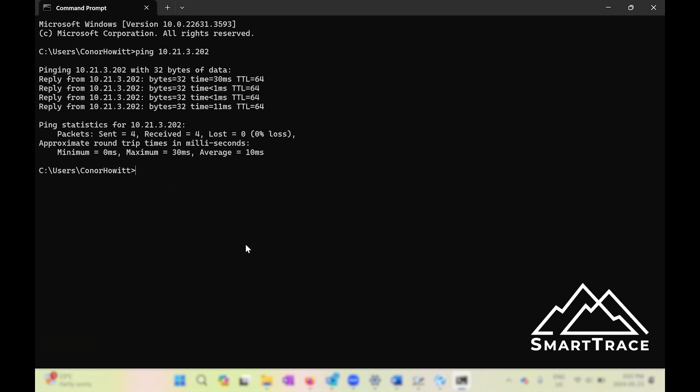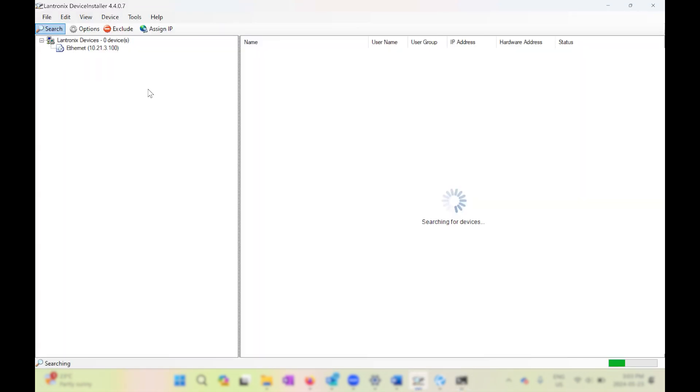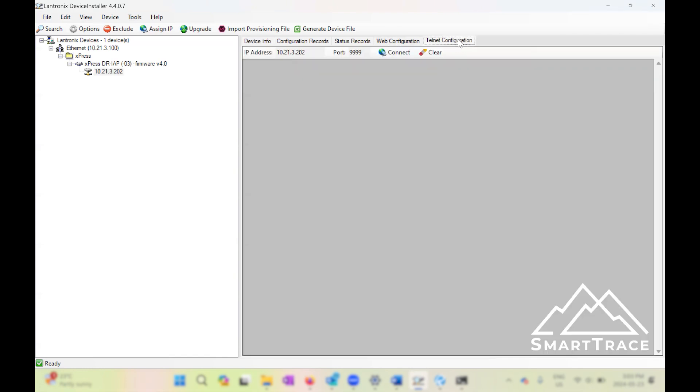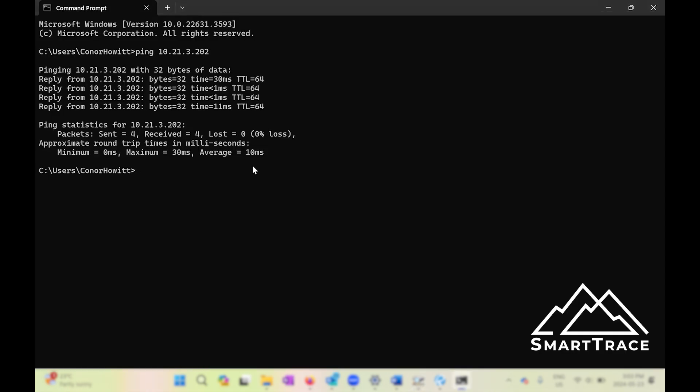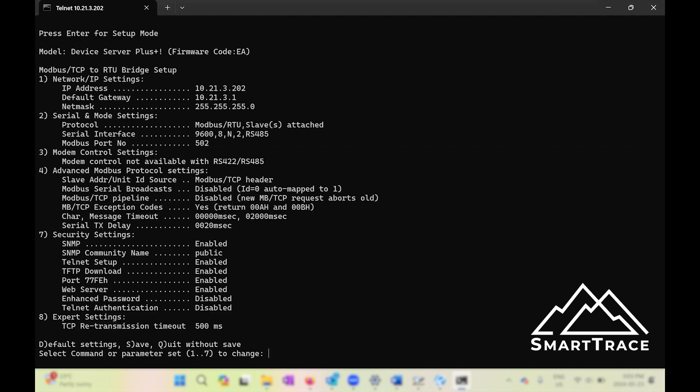To program the Lantronix device there are really two methods — both achieve the same result but use two different tools. One is using the Lantronix software called Lantronix Device Installer: you boot it up, do a search, and it finds all connected devices. There is a web configuration tool, but we typically use the Telnet configuration tool. What we find simpler, with no additional software required, is just using command prompt — type Telnet, then the IP address of the device, then port 9999, hit enter, and it brings you into the Telnet screen. Press enter for setup and this is the screen we want to see.